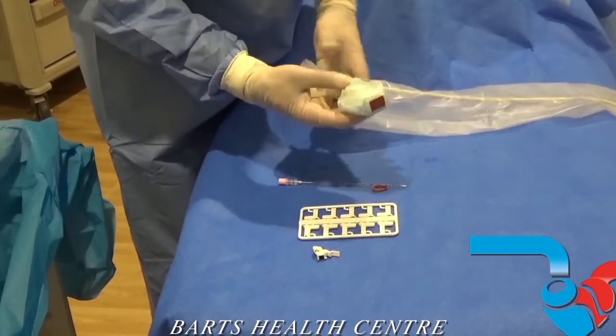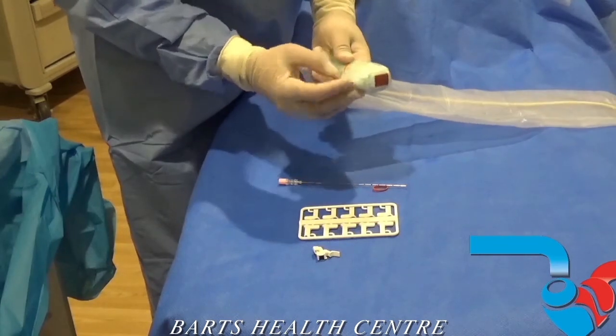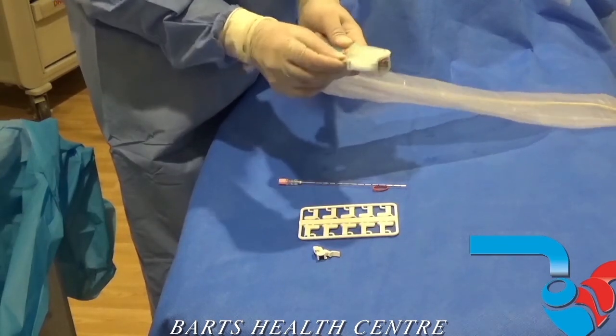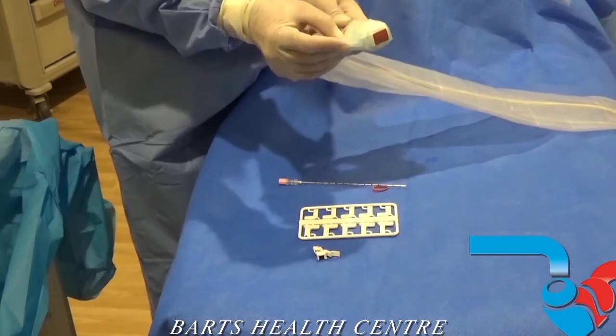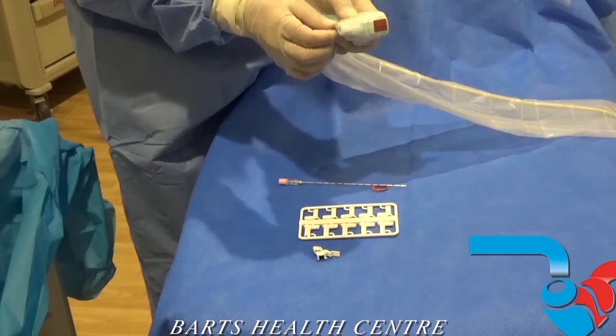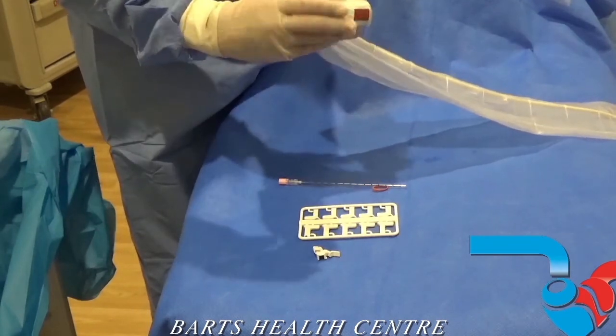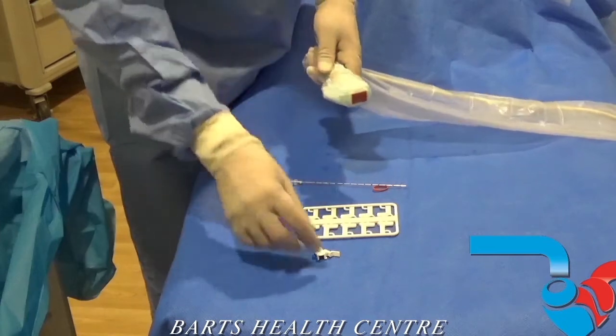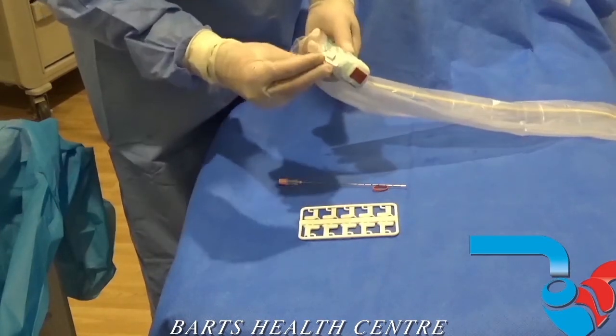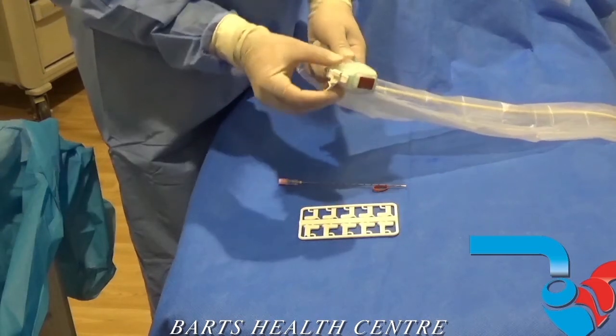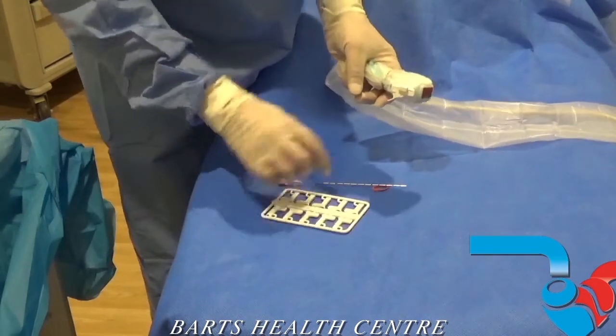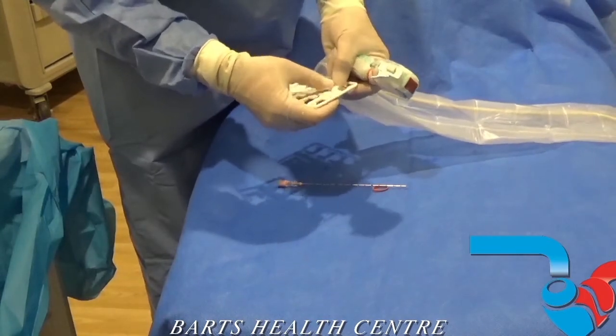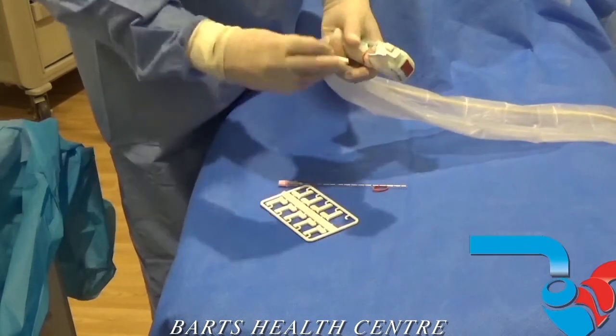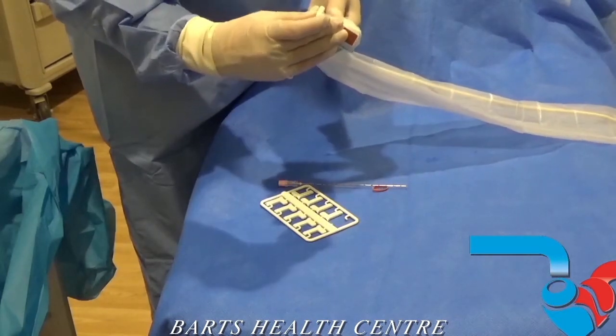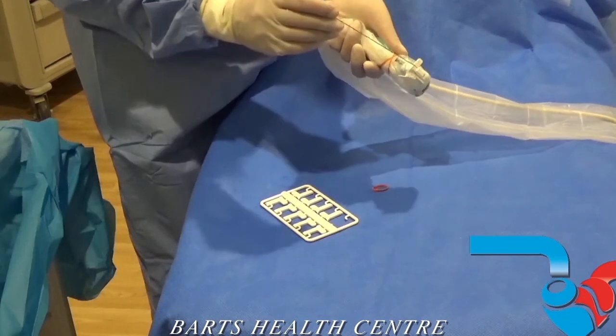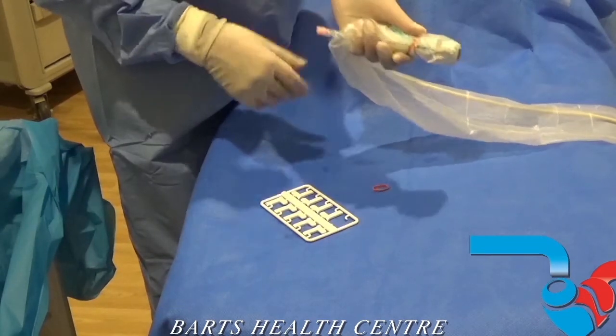So the sterile pack portion of it is here. We've now got a sterile sheath cover over the non-disposable bracket, and that's ready to go. It's adjustable, so that clips on, but this bit here is adjustable so that we can change the angle of approach with the needle, should we desire. This is the bracket that comes on with a clamp that just clamps on over the top of the sterile sheath, and that's now pretty secure. This is a 14 gauge needle, so we're going to pick out the 14 gauge insert, and that just slots in. That then allows us to slot in the needle that we're going to be using, and we're now ready to go.